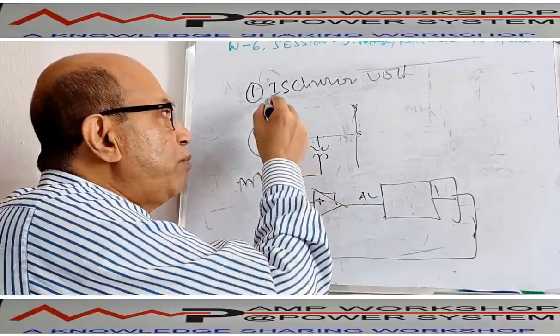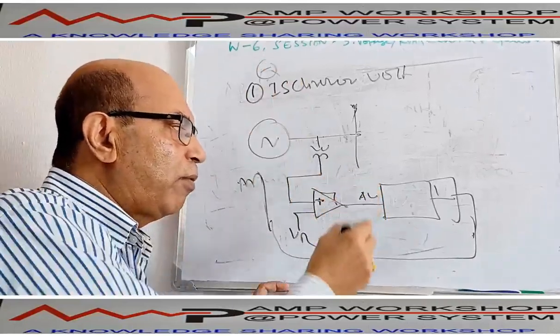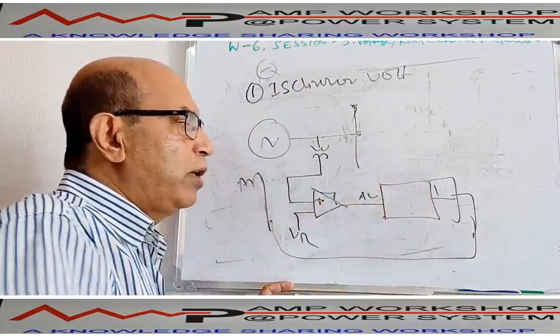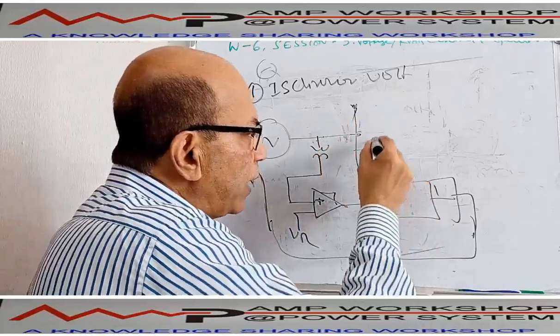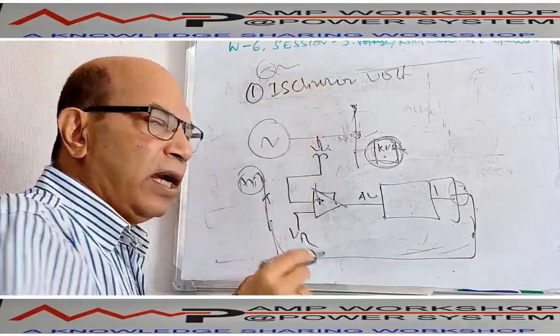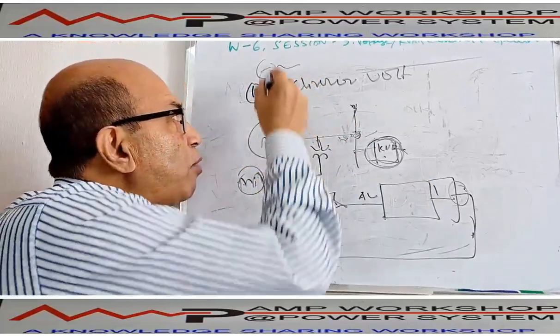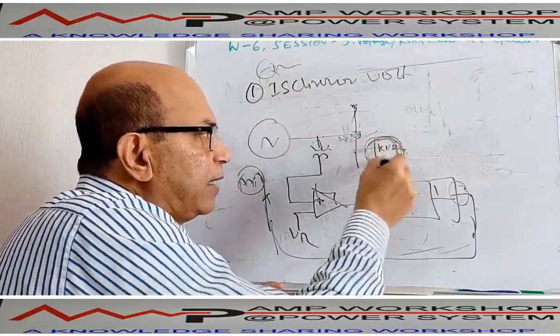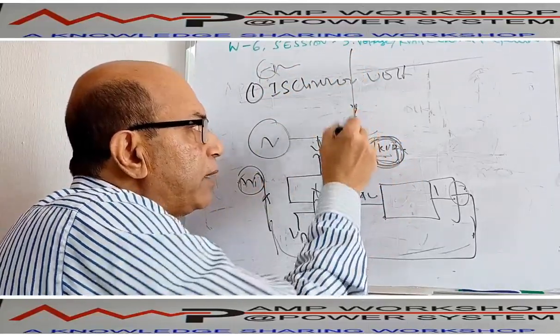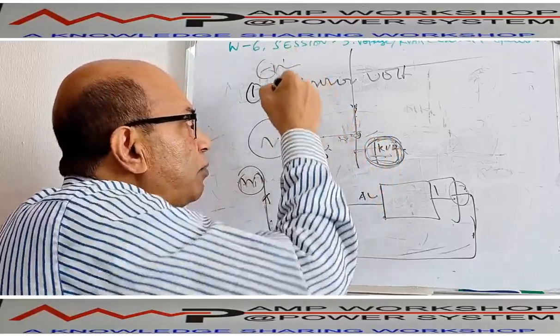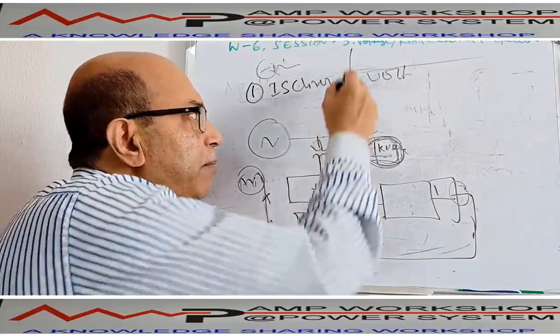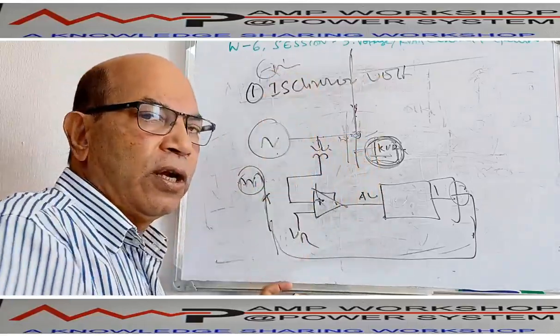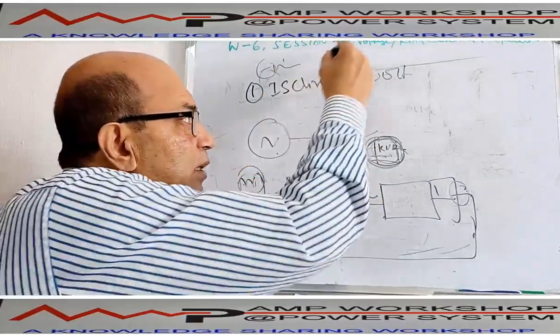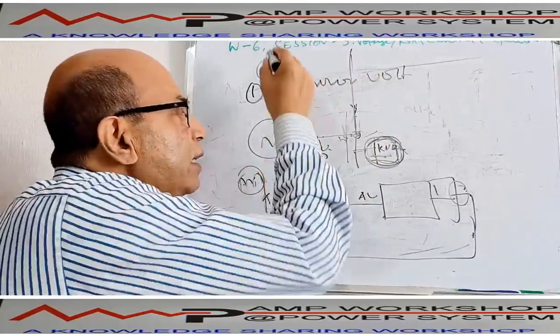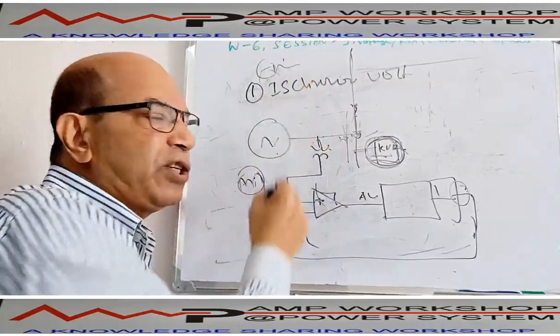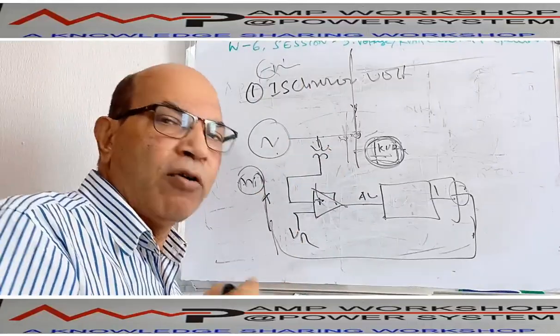But in this mode, if you put multiple machines, the problem is, who will control the voltage? The moment you increase the load over here, if you put multiple machines, the same thing will happen. Then there will be competition. When there is an active or reactive load (KVAR load) on the bus bar, suppose three machines are running, then all three bus voltages will drop immediately. All three machines will try to increase the voltage, and then there will be competition amongst them. Who will take the load and how much will it take?